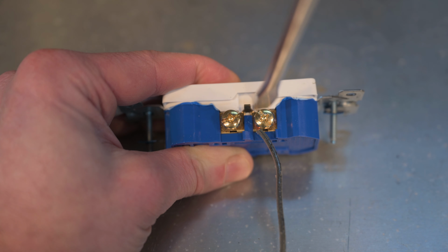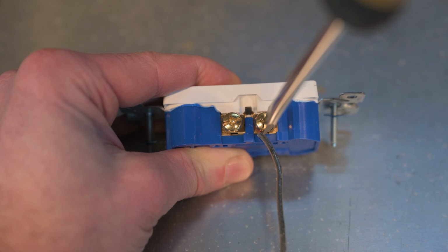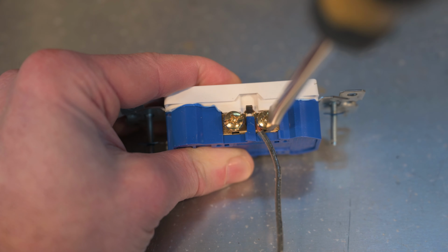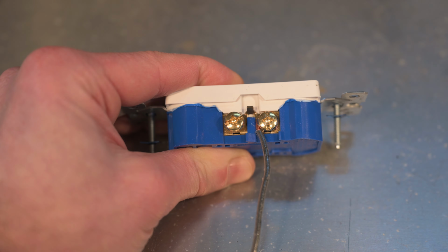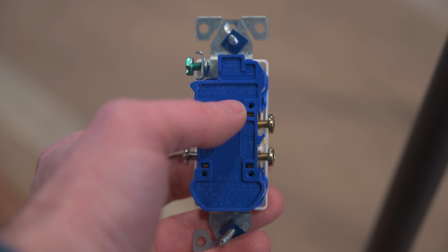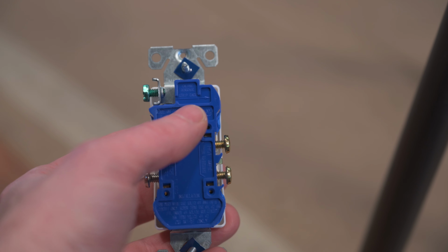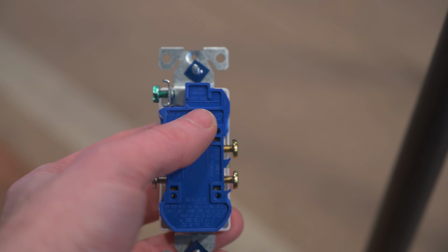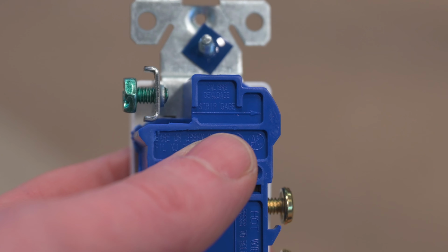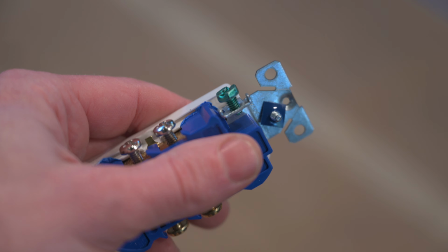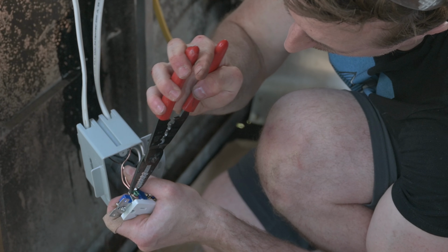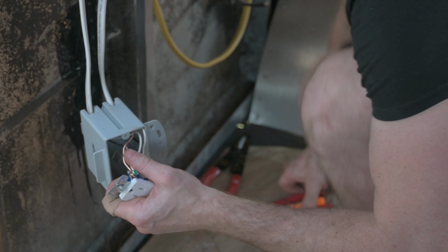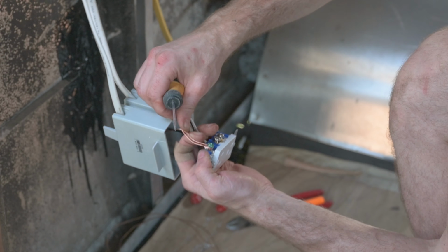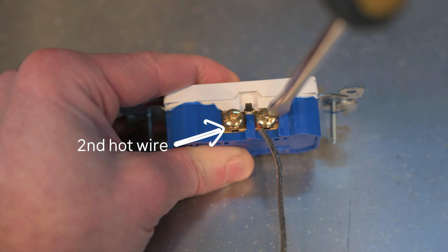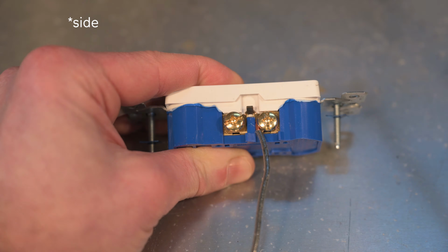With screw terminals like these, I bend a clockwise hook into the wire so that when I tighten the screw, it tightens the hook. If you're connecting it to a 14 gauge wire, they also have little holes in the back that you can simply push the wires into. Here in the back is a little guide that shows you how much insulation you need to strip off. In either case, the green screw here means ground, so attach the bare copper wire here. If your circuit continues to another electrical box, you can simply connect those wires to the second set of terminals on the side of the outlet.